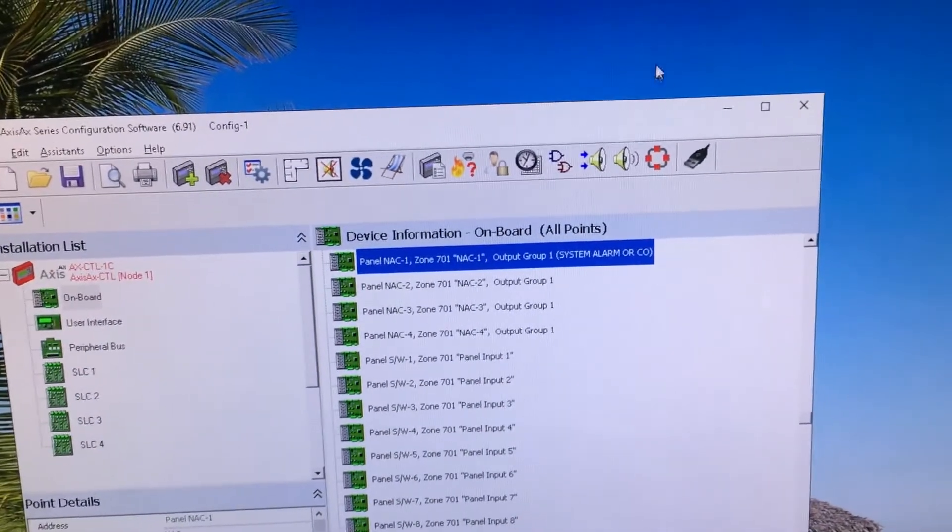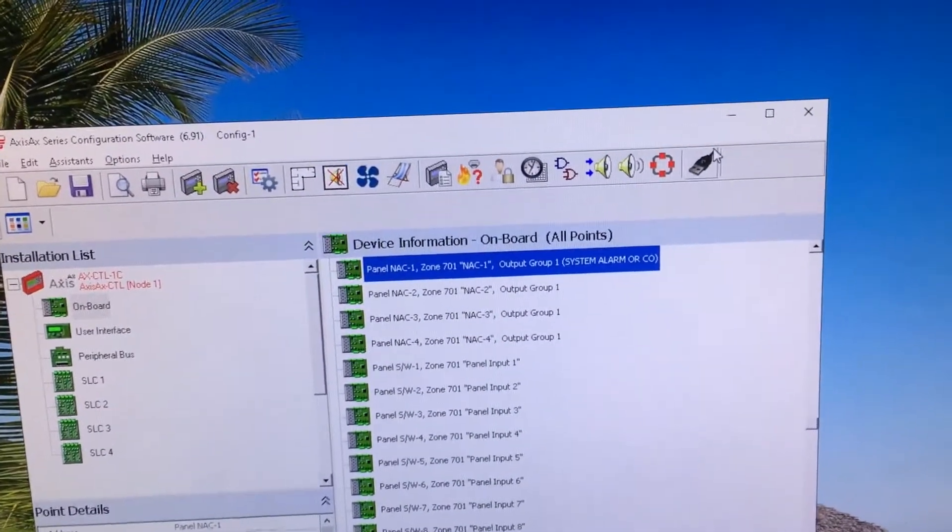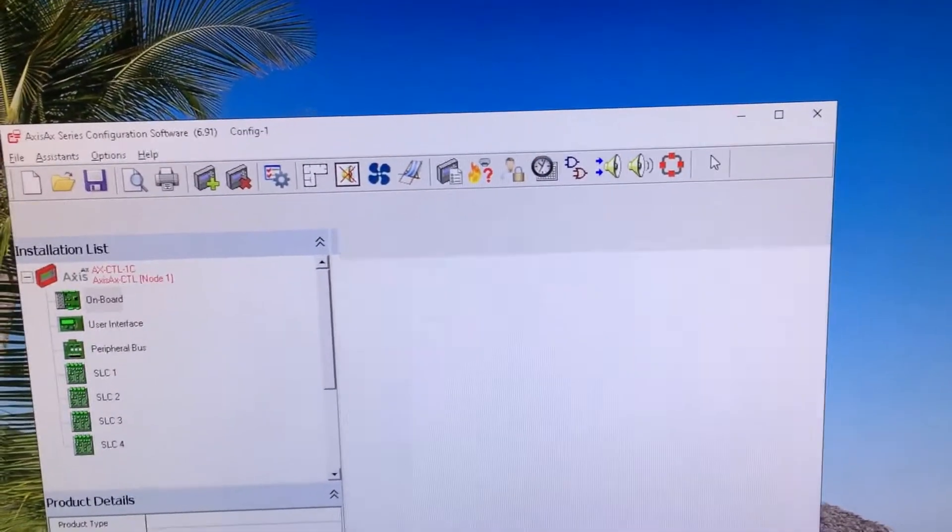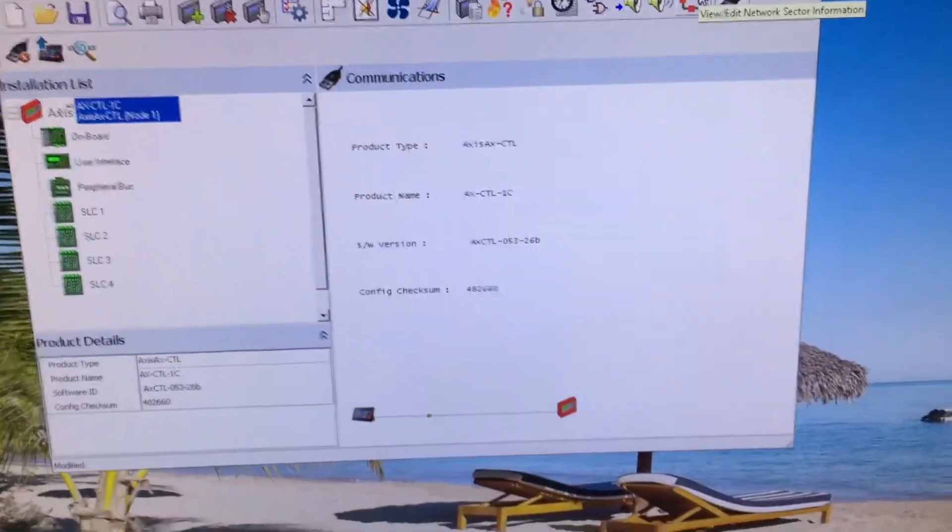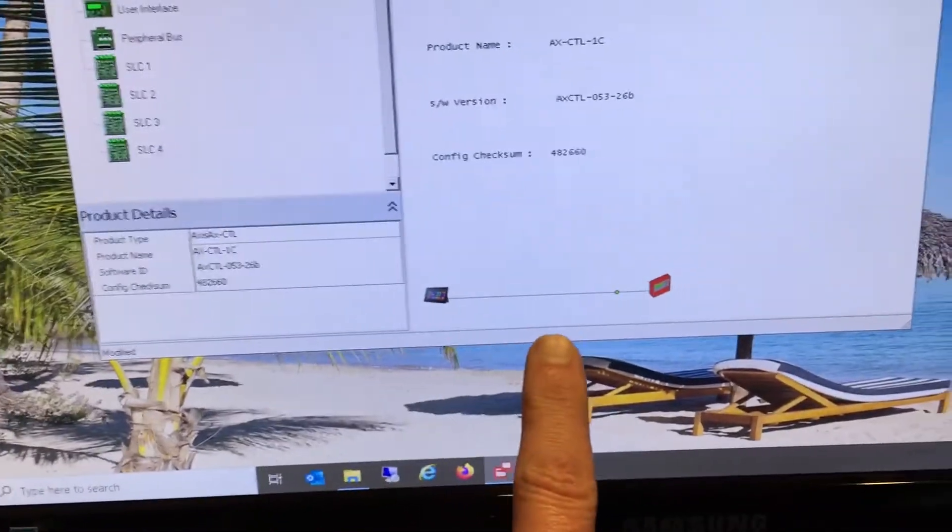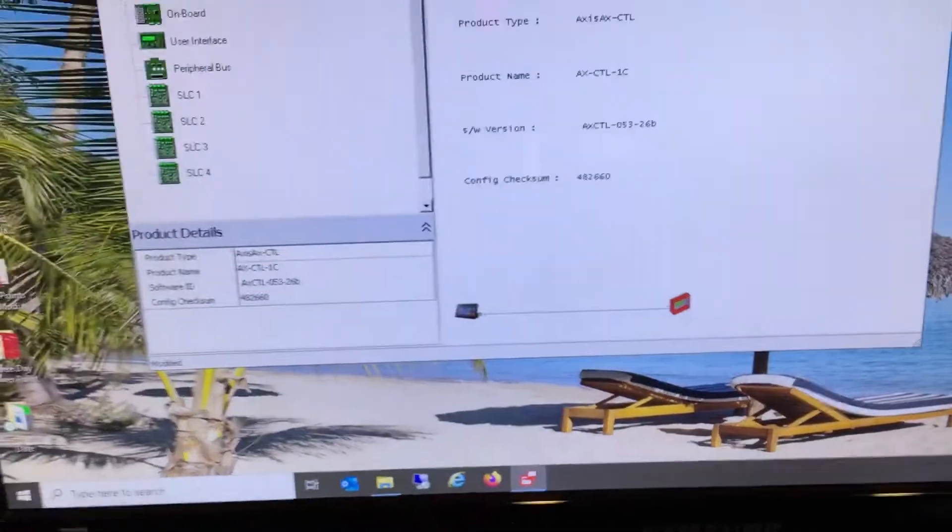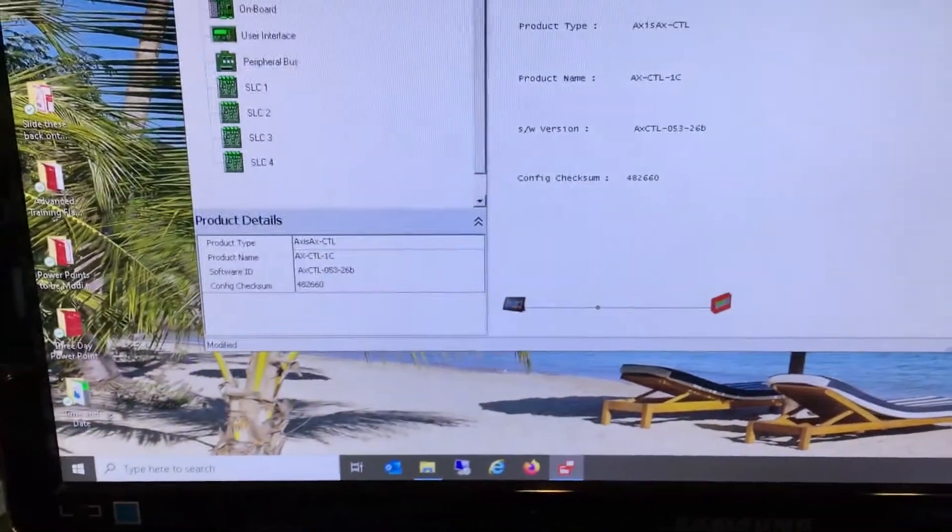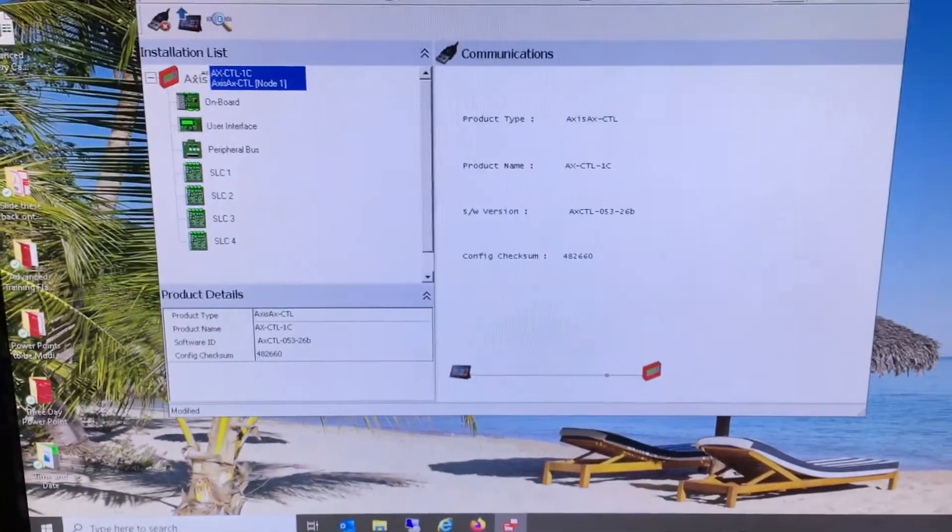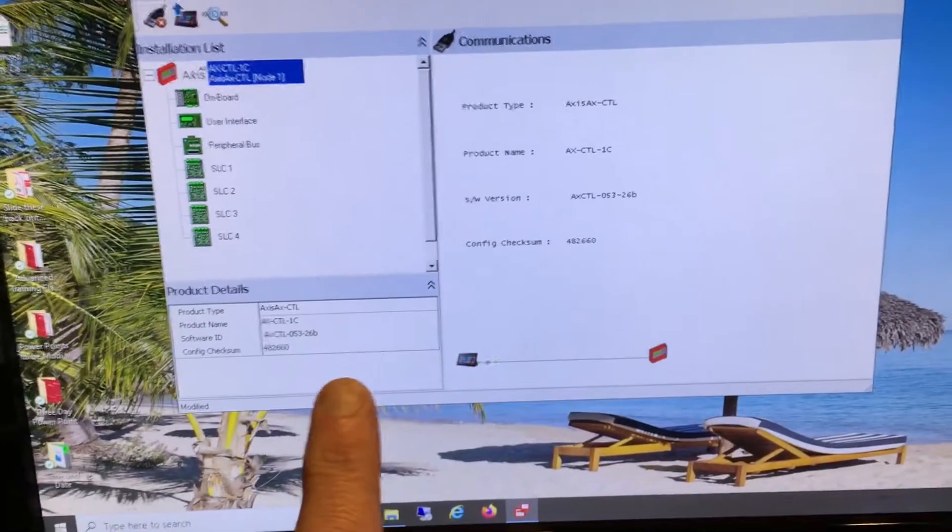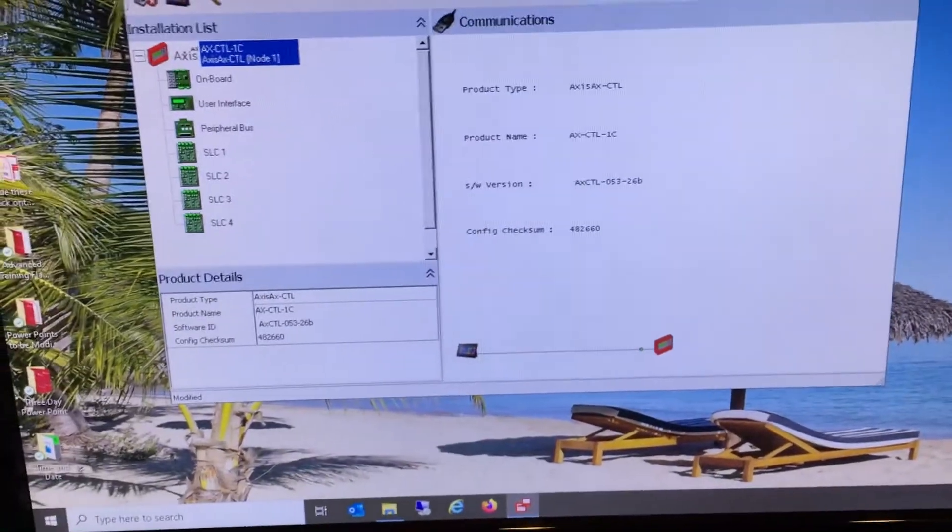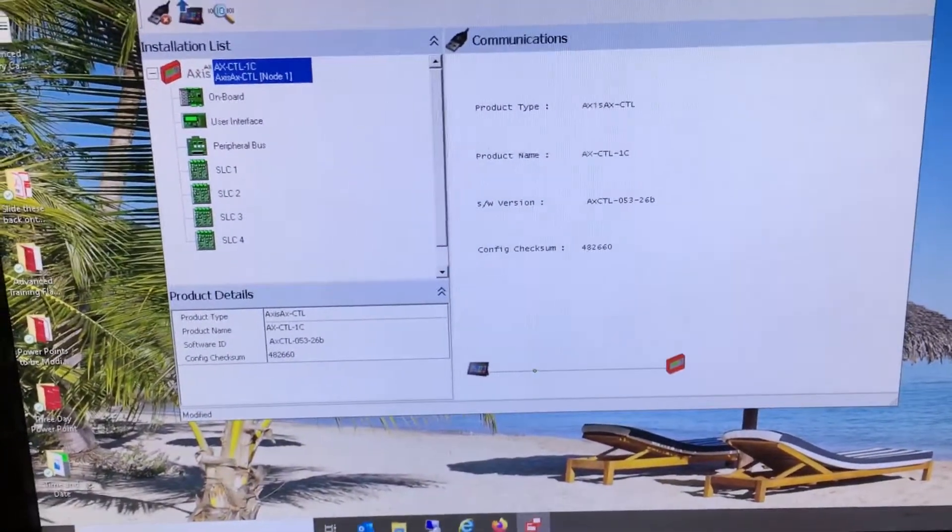I closed off the assistant screen. Now what I'm going to do is try to establish communications with the fire panel. As you can see down below here, I have communications. There's one other step that I need to do before I can take the information in here and put it into the fire panel: I must put the fire panel in PC config mode.